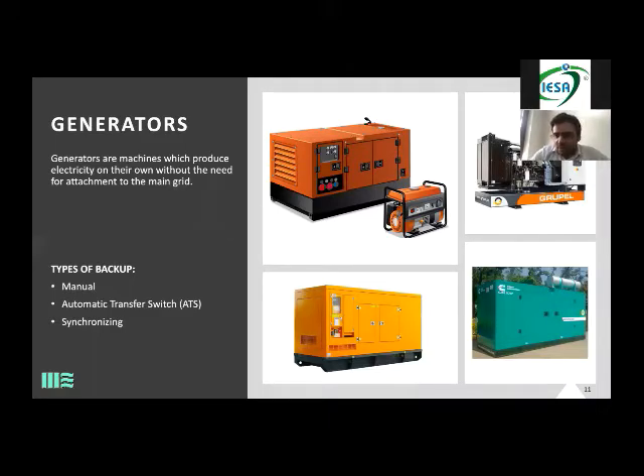Got it. Just to give you an example, last month, in the month of February, we did Namaste Trump. It was a high profile show. There can't be a flicker when Trump is on site or Modi ji is on site. So what we did, in total my load was 7,000 kVA. We got 1250 into 4 numbers plus 500s and all. Everything became a backup of each other. The whole show, sound, light, LED, delays, AC, everything had a backup. Got it. So reliability becomes very high, efficiency becomes very high. That is the whole benefit of synchronization.